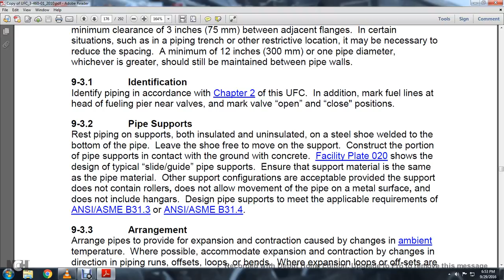9.3.3 Arrangement. Arrange pipes to provide for expansion and contraction caused by changes in ambient temperature. Whenever possible, accommodate the expansion and contraction by changes in the direction of the pipe run, offsets, loops, and bends. Where not possible, use expansion loops, offsets, or flexible ball joint offsets.